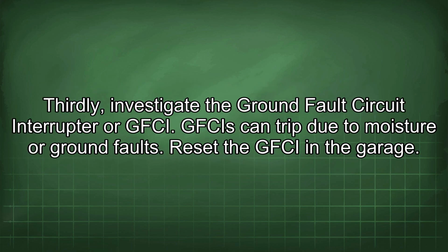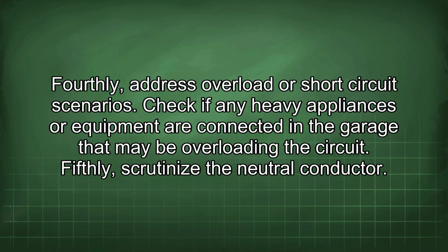Thirdly, investigate the ground fault circuit interrupter, or GFCI. GFCIs can trip due to moisture or ground faults. Reset the GFCI in the garage. Fourthly, address overload or short circuit scenarios. Check if any heavy appliances or equipment are connected in the garage that may be overloading the circuit.